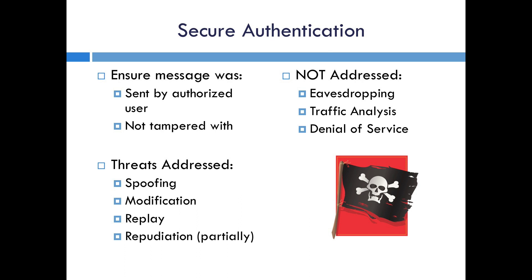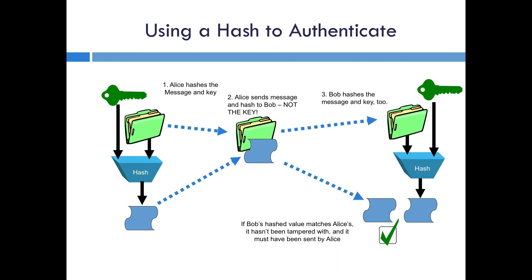What's included in secure authentication is the capability to do authentication at the application level and to address threats like spoofing, modification, and replay. The secure authentication mechanism is based on the concept of a cryptographic hash. A hash is a function like a cyclic redundancy check, or CRC, or a checksum that when performed on the message produces a much smaller string of numbers. This smaller hash value is very sensitive to changes in the message, but it's virtually impossible to determine the original message if all you have is the hash value.